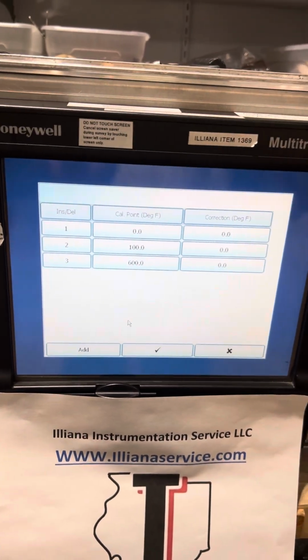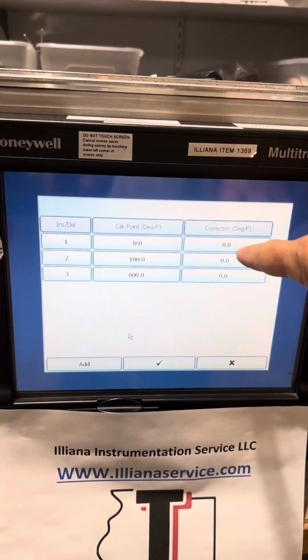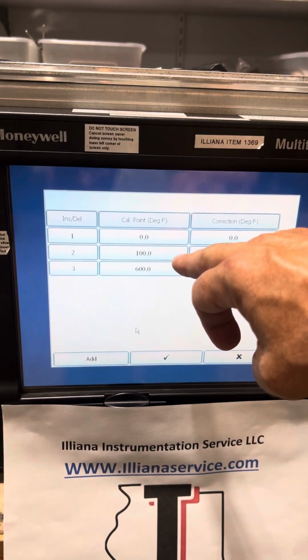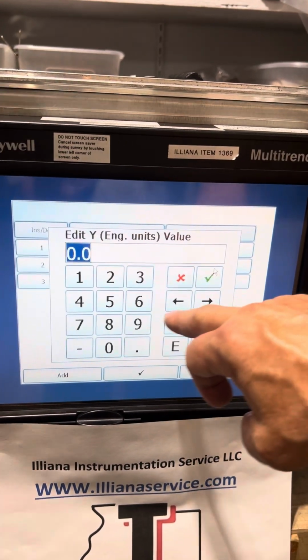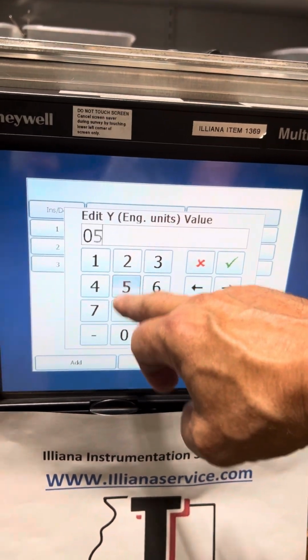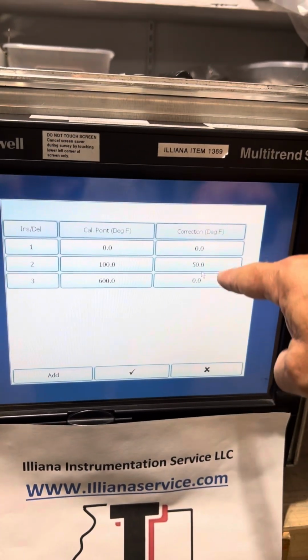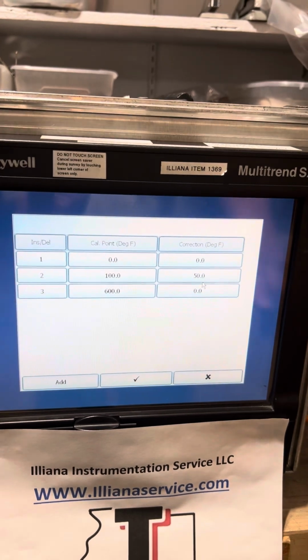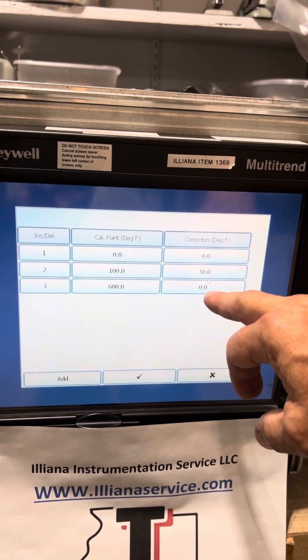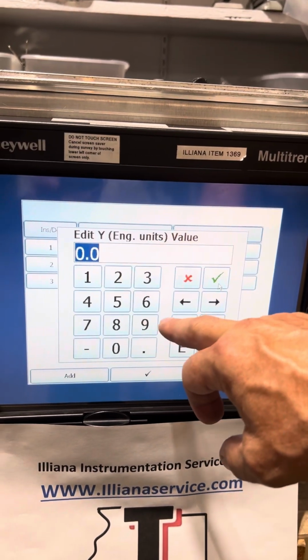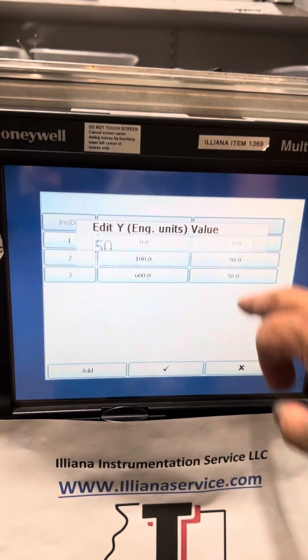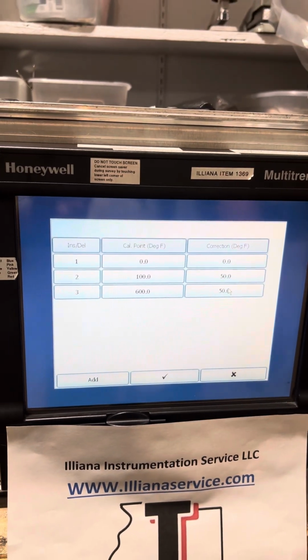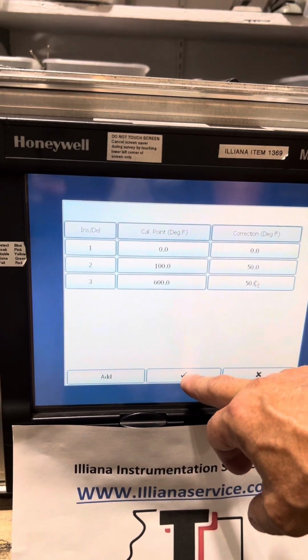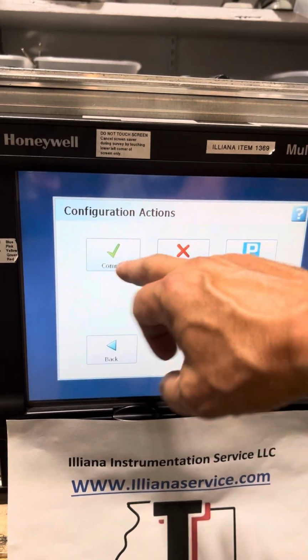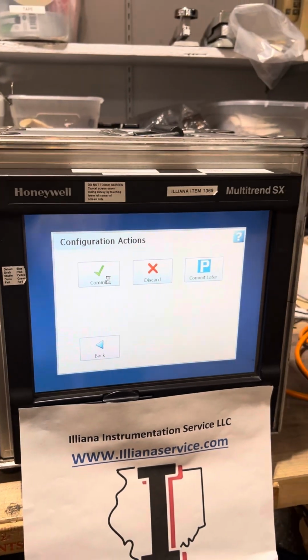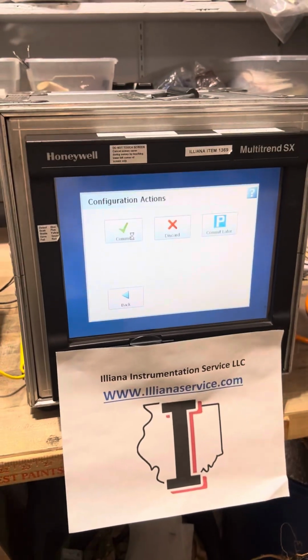So if you bought wire from someone and they said, hey, at 0 degrees this wire was perfect, but at 100 degrees this wire was off, and they gave you a correction factor of 50 degrees, which obviously is ridiculously large, but I'm just using it for demo. And at 600 degrees, it had an offset of 50. You could put those numbers in there, and that is going to correct for the fact that your thermocouple wire is not perfect. Now I have two corrections in there.